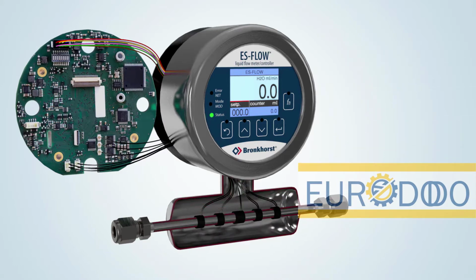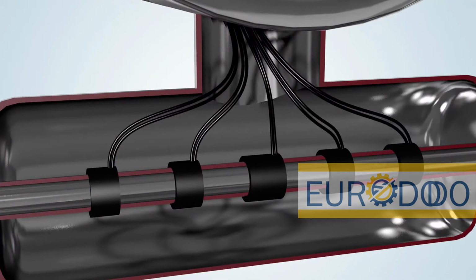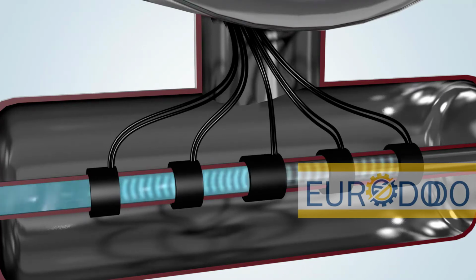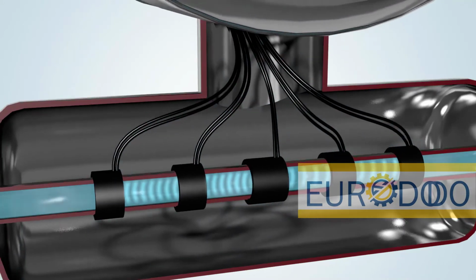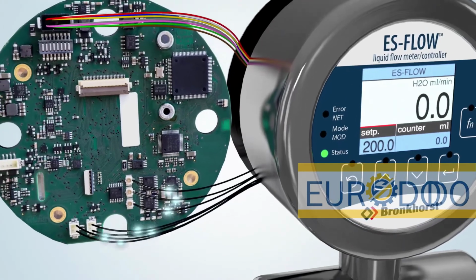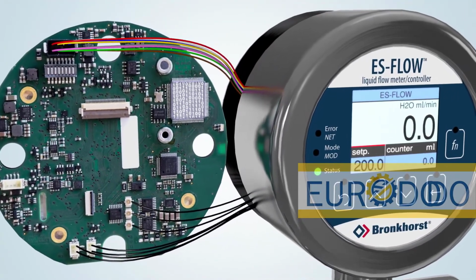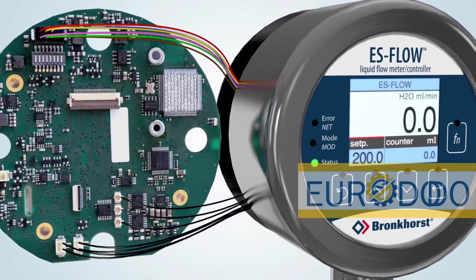Measuring is done in a straight stainless steel tube with a very small inner diameter. At the outer surface of the sensor tube, multiple transducer discs are located, which create ultrasonic waves by radial oscillation. Every transducer can send and receive these high-frequency waves. Therefore, all up- and downstream combinations are recorded and processed. By using the determined speed of sound and the calculated flow velocity in combination with the exact cross-section of the tube, the ES-FLOW is able to measure volume flow.